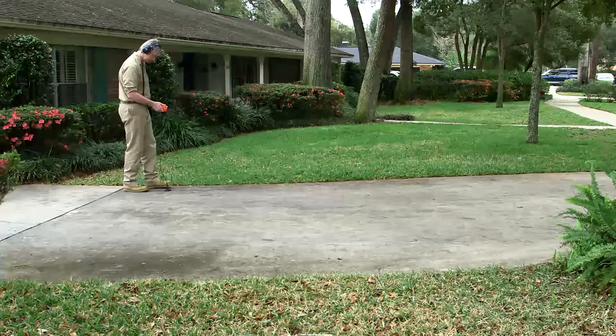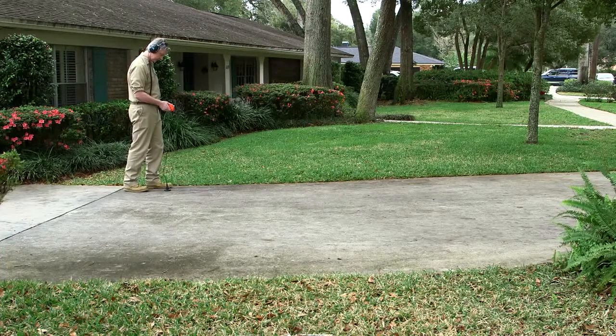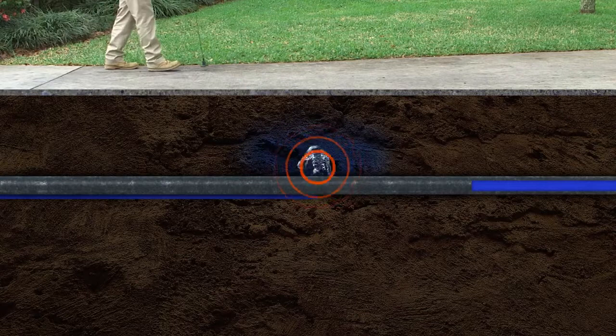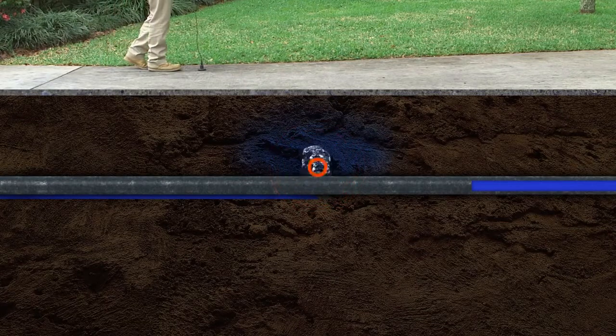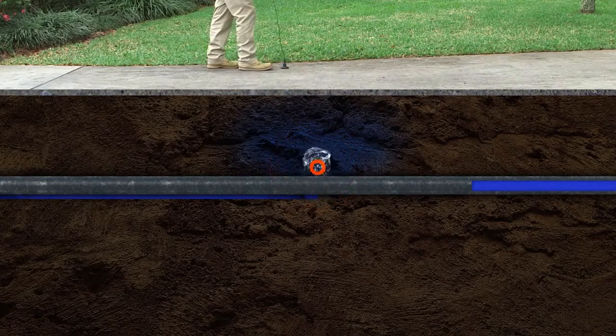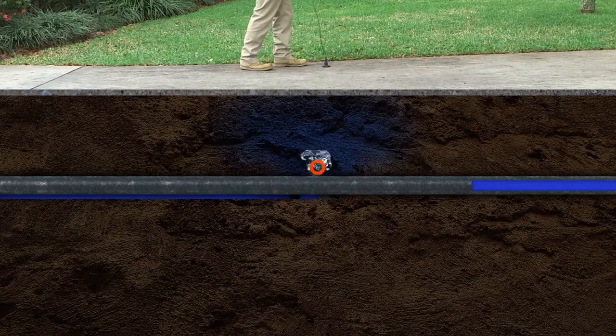Let's start with the inside line on leaks. Leak sounds are created by three different situations. One: the vibration of the pipe caused by water forced through a crack in the pipe. This is the loudest and easiest leak to detect because it sounds like a little whoosh or hiss.